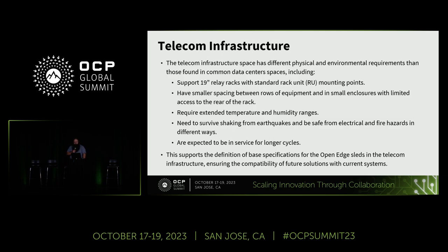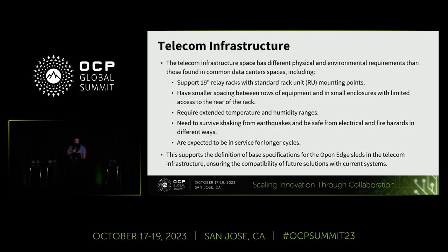The original infrastructure is constrained by physical and environmental requirements. This is built on what has traditionally been the NEBS specifications. As we move this into a more general computing environment and into constrained edge cases, it requires things that go beyond NEBS, which was designed for your traditional central office environment. The specification supports a 19-inch relay rack with standard rack unit mounting points, and it has smaller spacing between rows of equipment to address those small enclosures.